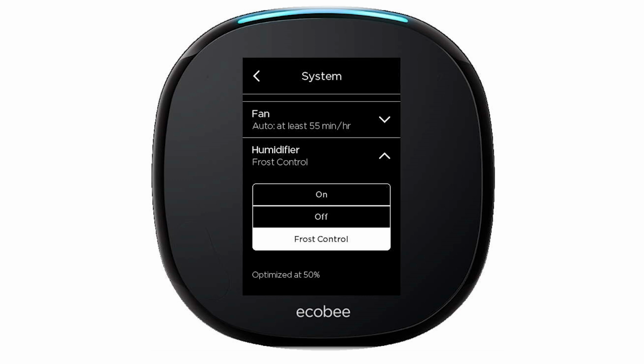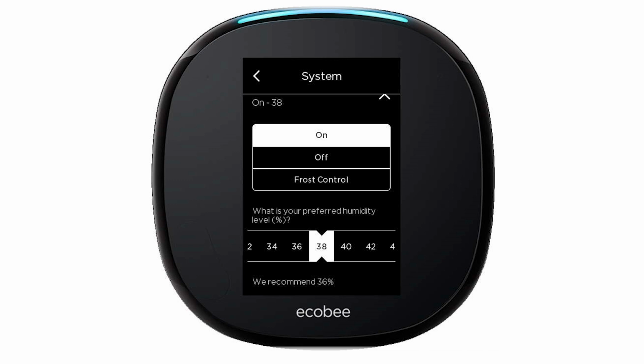With the humidifier, I've wired this thermostat up to utilize all stages. So it's a 2 heat, 2 cool with a heat pump. And we've also got a humidifier wired up. With the humidifier, you're going to be able to go in and adjust that here, turn it on. It's going to ask you to set your preferred humidity level, usually somewhere around 40%. We recommend 36. It's going to depend a lot on the time of year.